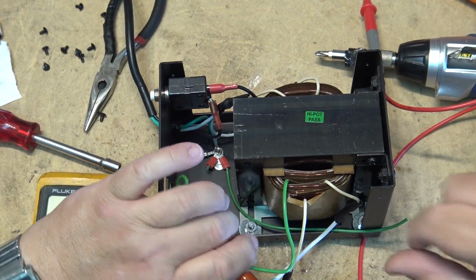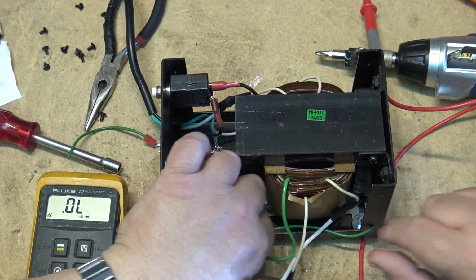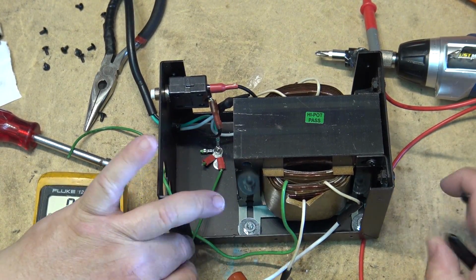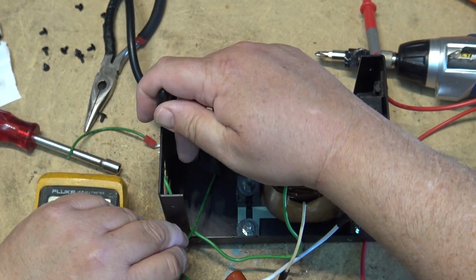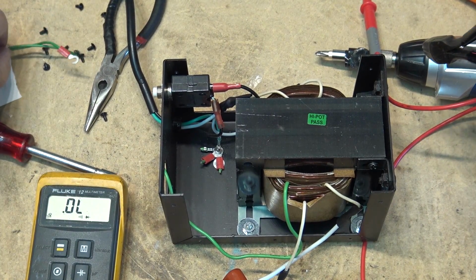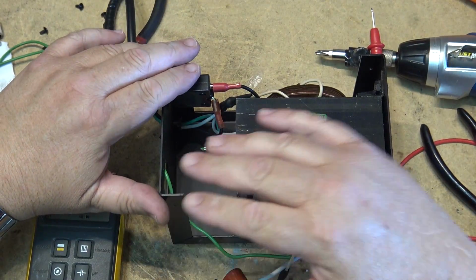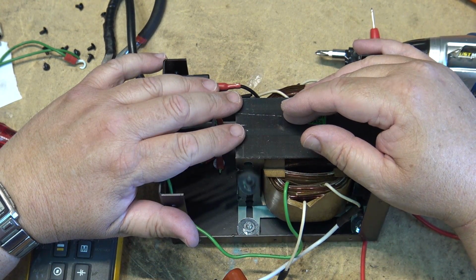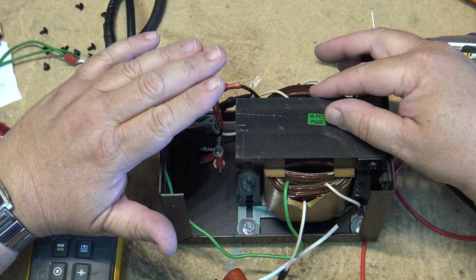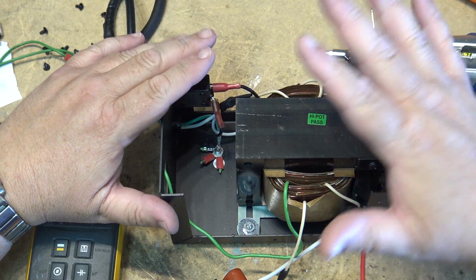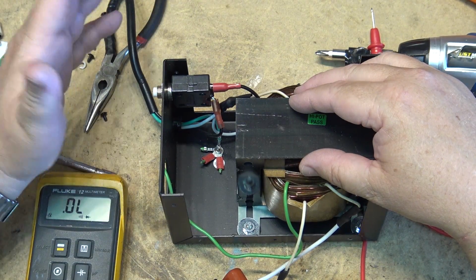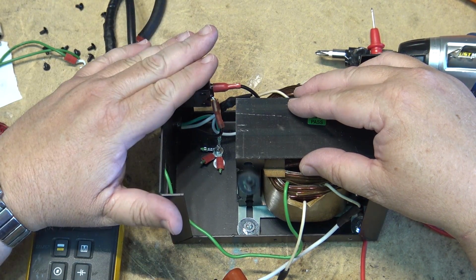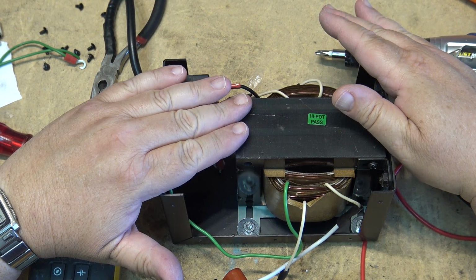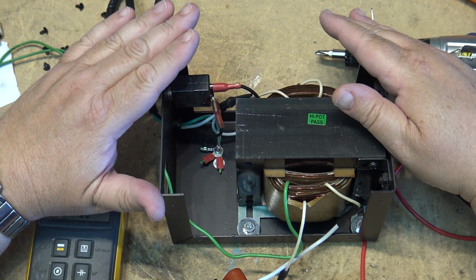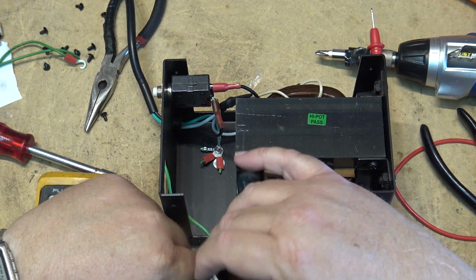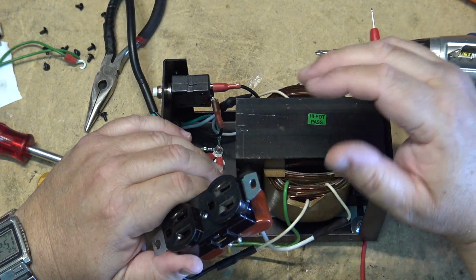Now I know people are going to say, oh, you're defeating all the safety. I'm not defeating the safety. This type of transformer is what they call a medical grade isolation transformer. What it does is isolate the equipment from the line by means of a transformer, with the effect of trying to prevent power surges, because the transformer will saturate and absorb a lot of power surges, but they still pass the earth through. And for a service bench, you don't want the earth at all connected to this plug. You want both sides to be completely isolated.